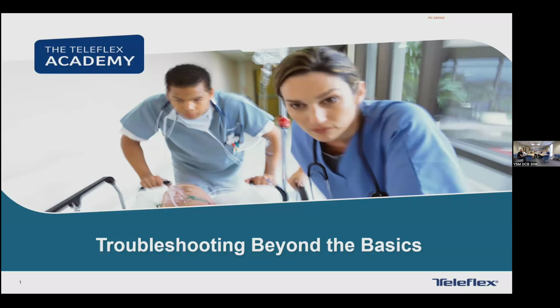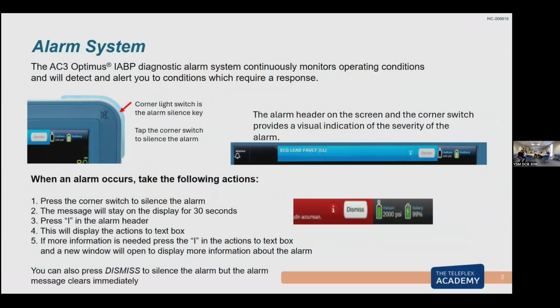First off, we have an alarm system on our pump that never shuts down. It doesn't shut off for any heart rate or any conditions. It's always monitoring the helium on a beat-to-beat basis. We have several levels of alarm. The lowest level is just a message alarm. It'll be a blue banner that comes up on the screen. The pump will still be pumping, but there's a message. Maybe a lead came off, maybe a low helium tank. The pump is still pumping, but it says there's something you might need to check.